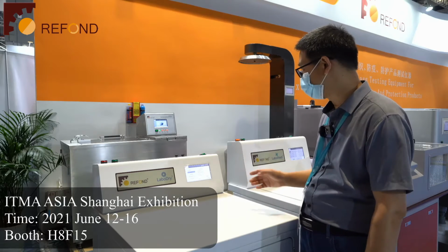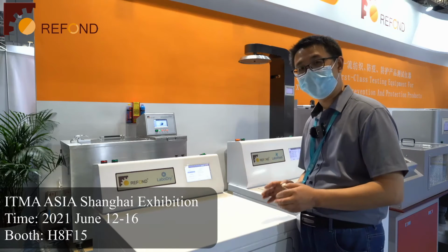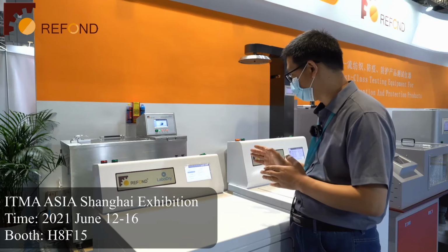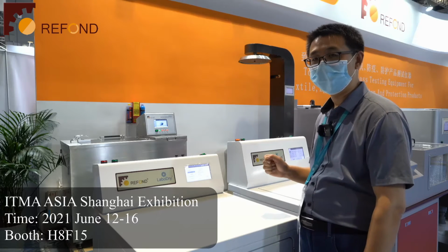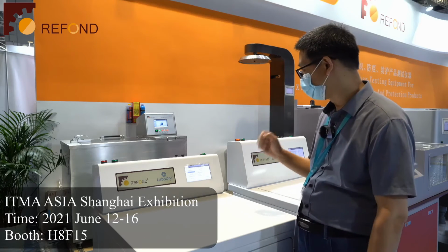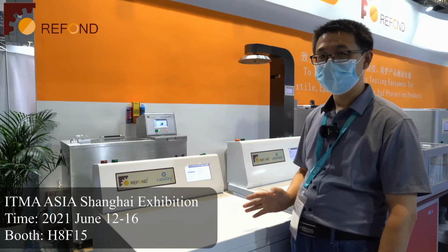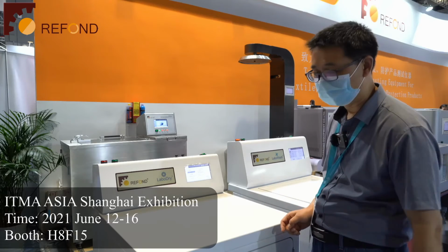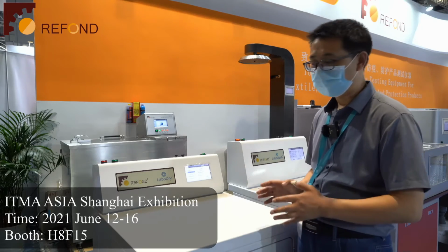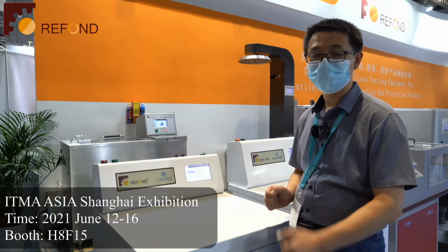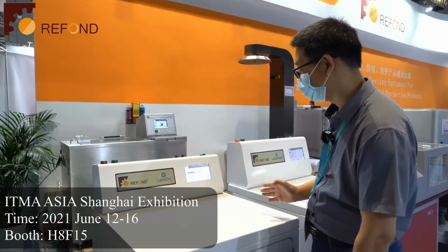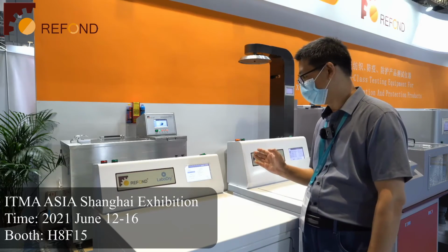After the customer has the experience, they can decide what is the targeted humidity they want to set. Once they set the targeted humidity, they can control the drying condition of the specimens inside the drum. So it can protect the specimens inside from over drying or less dry. This is our new function of the drying machine. Let me introduce our rain test to you.